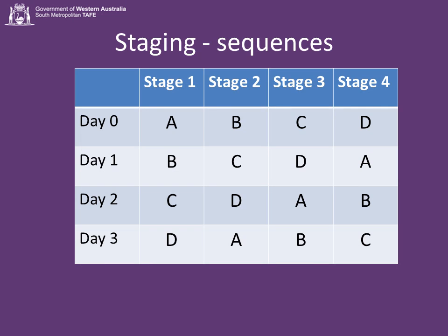To even out pump usage, I need to start them in different sequences each day. I'll need to find a convenient time to change sequences. Like I said before, I normally pick midnight because it's quiet time. So on day 0, I'll start them up A, B, C, D. On day 1, B, C, D, A. On day 2, C, D, A, B. And on day 3, D, A, B, C. This way, all the pumps would get equal use.